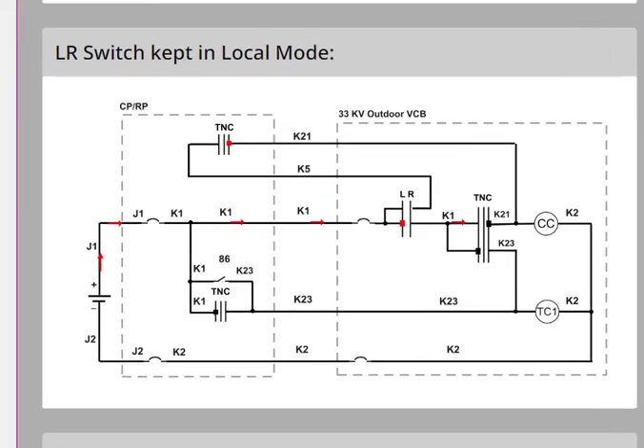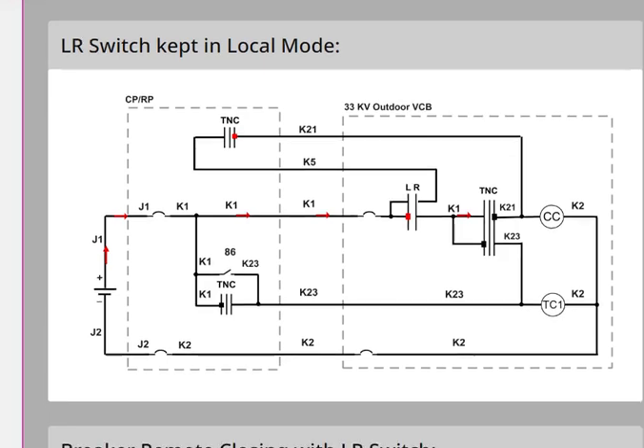Now we will see why we need a local remote switch. Suppose the breaker is under outage and we need to carry some work on it. If one person is working on the breaker and someone closes the breaker remotely from the control room, there might be an accident and he may lose his hand. So if we install a local remote switch and its local contacts are placed in series in the closing circuit, the breaker cannot be closed remotely once the local remote switch is placed on local.